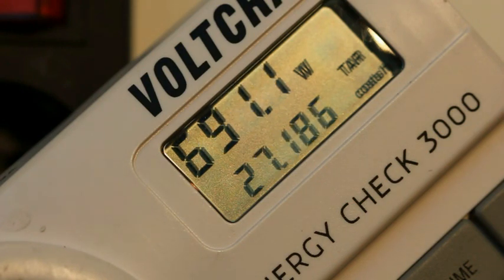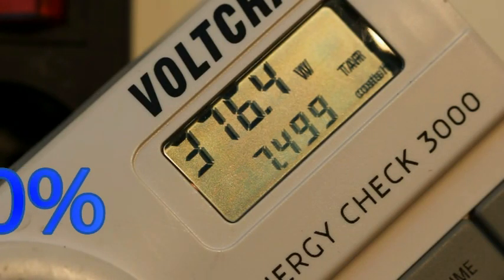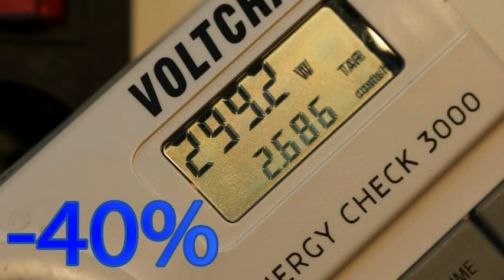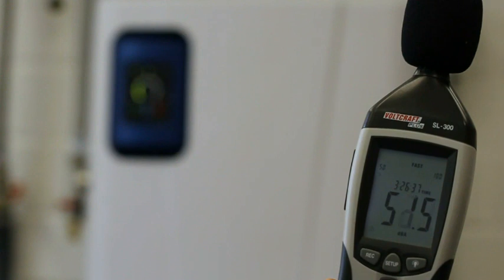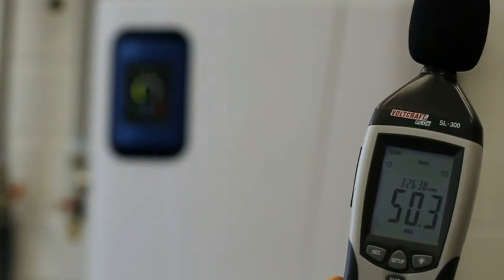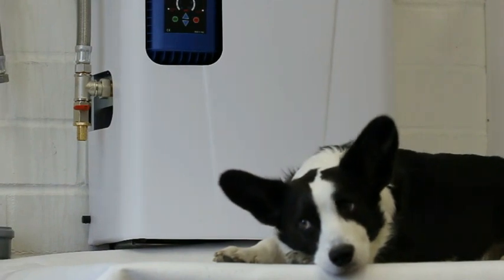The RainMaster Favorite with speed control model is equipped with a speed controller, which regulates the volume and pressure to the current demand and energy use. In practice, this saves up to 40% energy, meaning it already fulfills the strict efficiency standards of European Eco Design Directives. With speed regulation and special pumps, it creates 70% less noise than other comparable units.